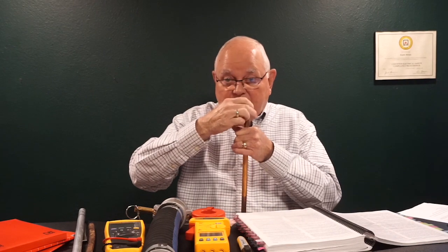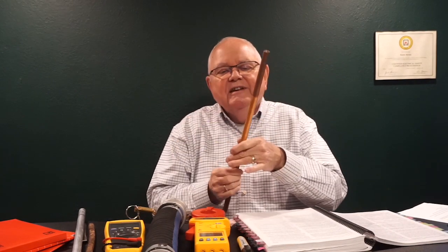What about this communication system and so on? So look in the appropriate part. If I need to know, how do I terminate? How do I ground? How do I install this grounding electrode? It has to be in contact with the earth for so many feet. That's not nearly long enough, is it? It's not near 8 feet.